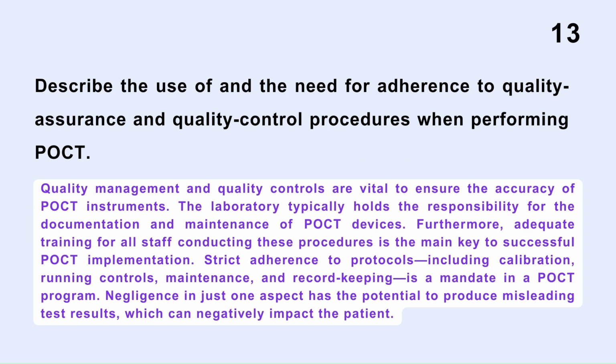Quality management and quality controls are vital to ensure the accuracy of POCT instruments. The laboratory typically holds the responsibility for the documentation and maintenance of POCT devices. Furthermore, adequate training for all staff conducting this procedure is the main key to successful POCT implementation. Strict adherence to protocols, including calibration, running controls, maintenance, and record keeping, is a mandate in a POCT program. Negligence in just one aspect has the potential to produce misleading test results, which can negatively impact the patient.